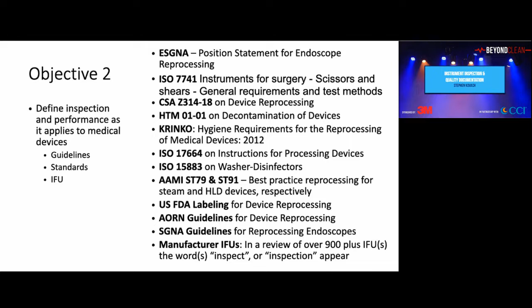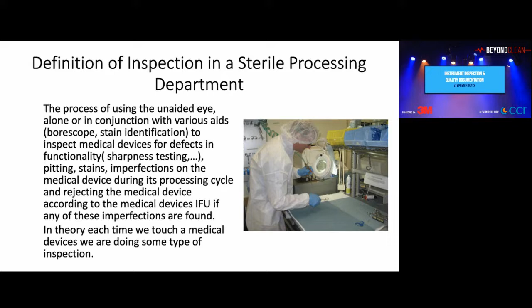So, the definition of inspection within our department: the process of using the unaided eye alone or in conjunction with various aids, such as a borescope, stain identification, or a simple magnifying glass, and in functionality, a sharpness test, leak testing, and so on, finding pits, stains, and imperfections on the medical device during its processing cycle, and rejecting the device according to the medical device's IFU. If any of these imperfections are found, it's rejected. In theory, each time we touch a device, we are doing some type of inspection. Whether it's a peel pouch, you're looking at that pouch as you put it on the shelf, take it to the room, or put it in a case cart. Is the pouch intact? Do the tips inside have a tip protector so it doesn't go through? How does it look? And so on.